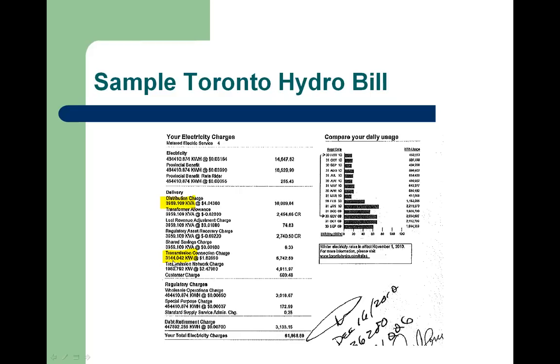So if you were to take that kilowatt here at 31.44 divided by 39.59, you would end up with the power factor, which I think in this case is in the 70s, around 70% power factor.